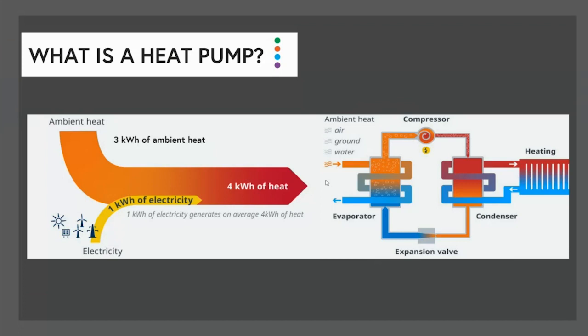So these are just round numbers, and they don't mean a lot. They're just there as an example, and it's not accurate that every heat pump makes 4 kilowatts of heat, but let's just use round numbers. So for every 1 kilowatt of electricity that's being used by the heat pump to function, it's absorbing about 3 kilowatts of ambient heat from the environment. Combined, that produces 4 kilowatts of heat delivered to the system, and that's an efficiency of 400%, or a COP of 4. Now COP is the coefficient of performance, and it's a rating number that indicates a system's efficiency.